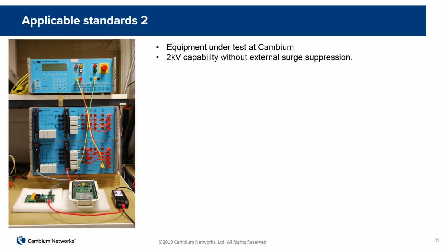So here is a piece of equipment under test. In this instance, we're testing at 2 kilovolts, and as I mentioned earlier on, the equipment is tested and shown to withstand 2 kilovolts without current flow. In other words, the isolation barrier isn't breached. If we were to test at a higher voltage, then we would need to add an LPU or some form of surge protection to the system.